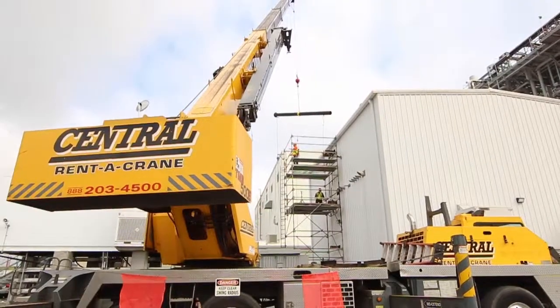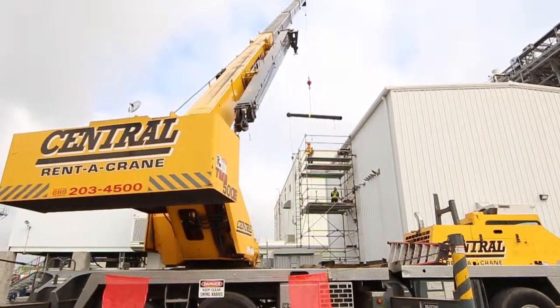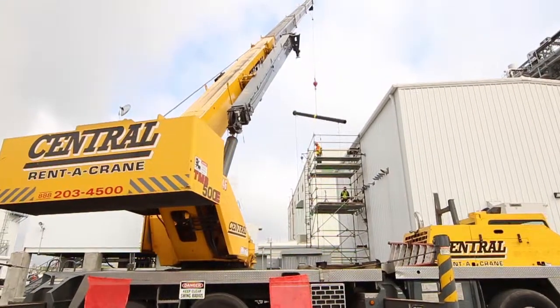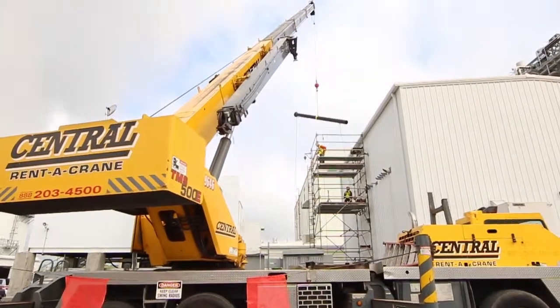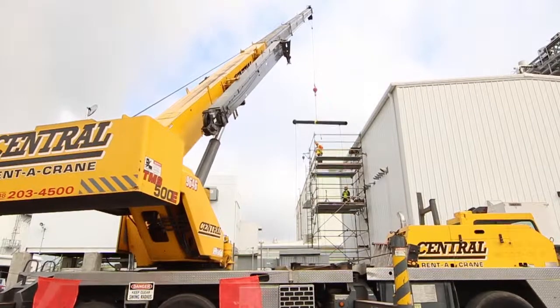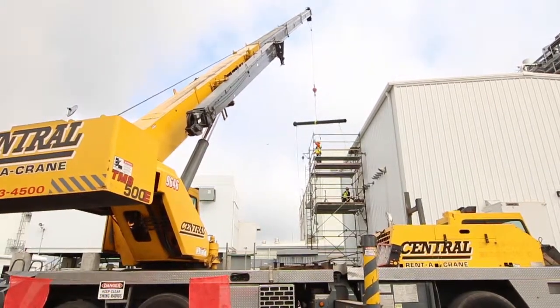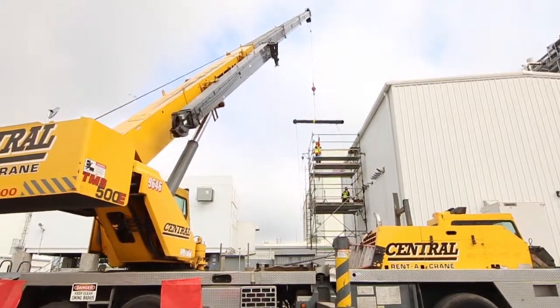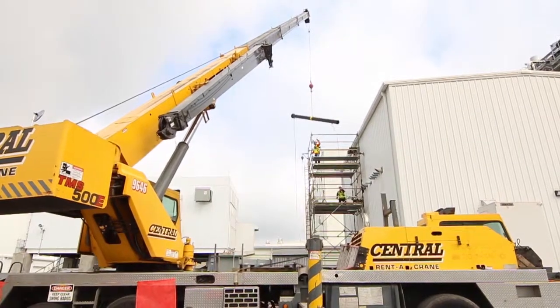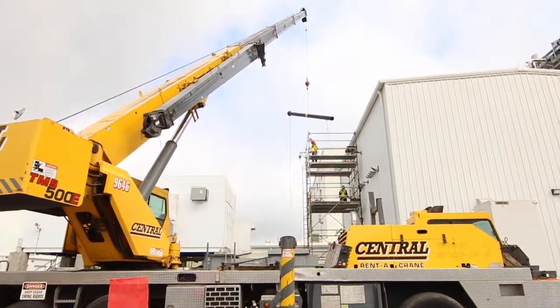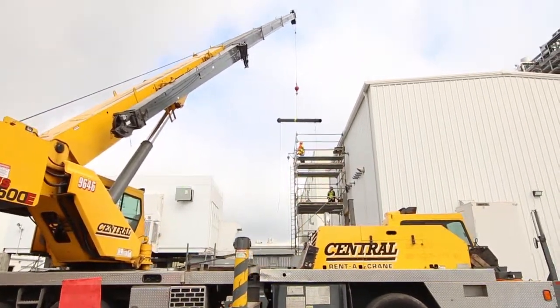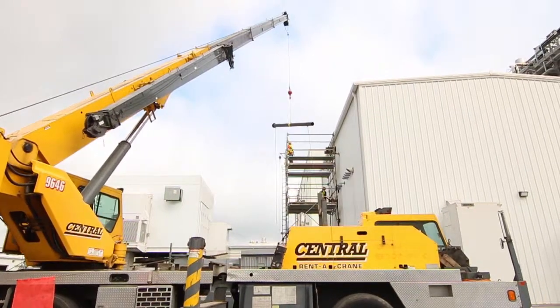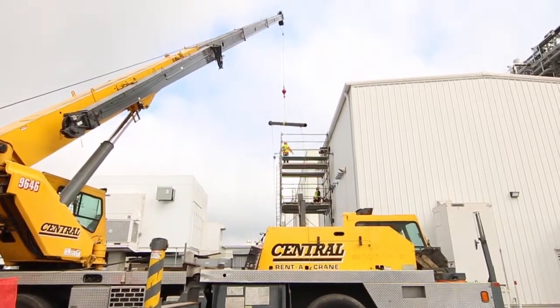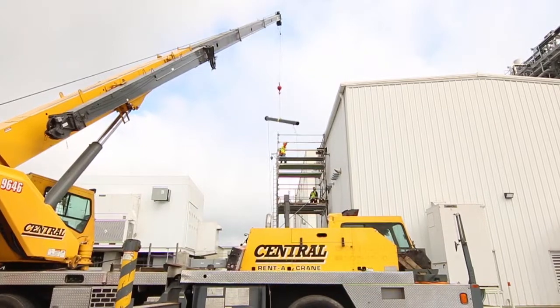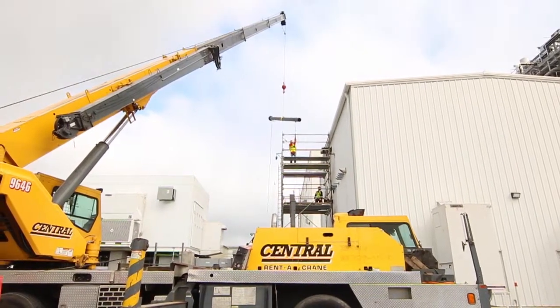If you are operating a mobile crane or any other boom-equipped heavy equipment requiring a boom to be extended near electrical lines or equipment, a qualified employee must first identify the voltage present, verify the electrical status of the lines or equipment, and provide you with the applicable safe work clearances you must maintain. If the voltage is unknown, minimum required clearance is 20 feet.